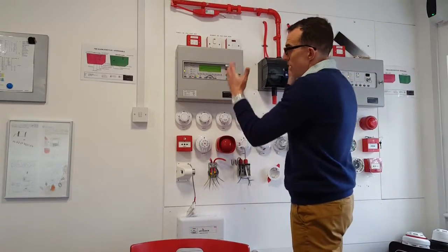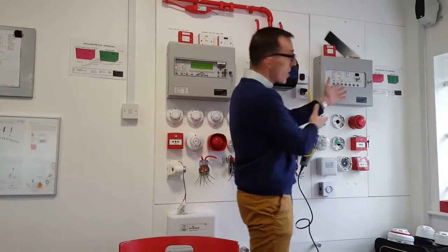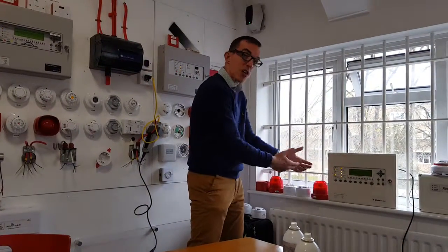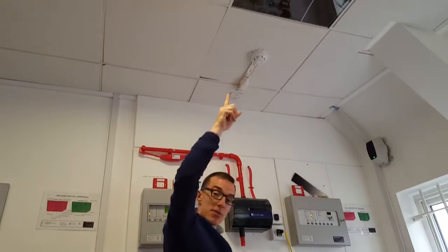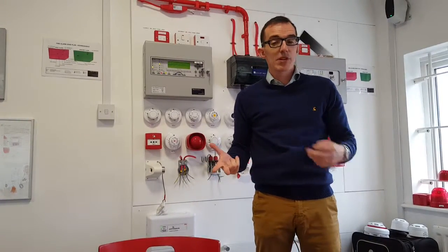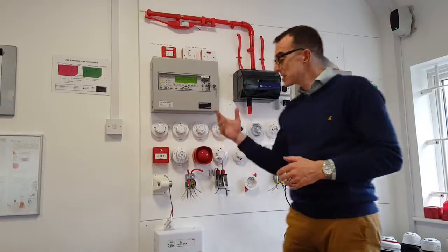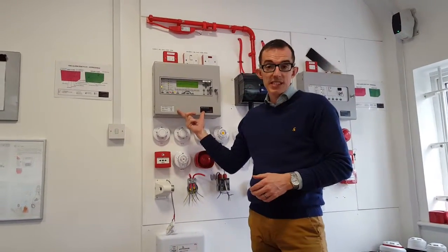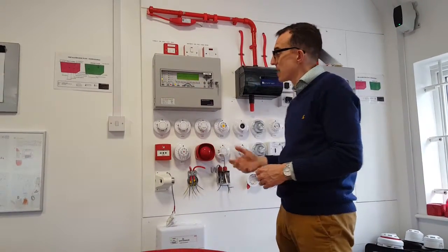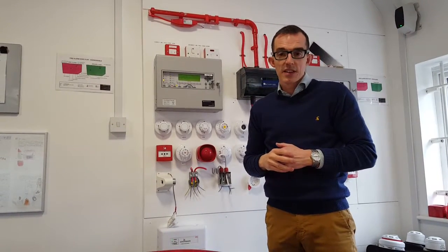So it doesn't matter whether it's an analog addressable panel, or a conventional panel, or a radio panel, or a hybrid panel where you've got a bit of both. It doesn't matter what you've got, it doesn't matter who makes it, or who manufactures it, or whose name is on the panel, you still have to test 100%. And we use our asset collection iPads in order to gain that information, so we know exactly what's on the system. So that's testing the devices, that's testing the batteries, that's testing the fire alarm panel, and then over and above all, we test everything. And that's kind of it, really.